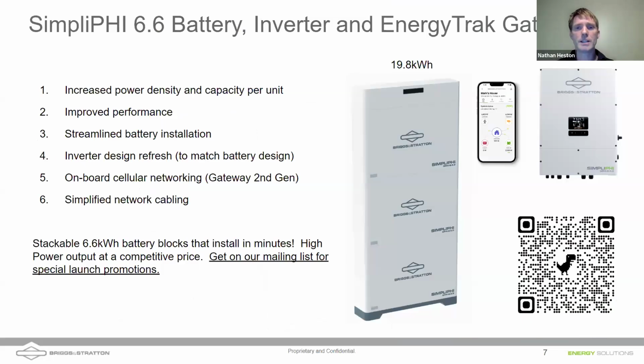So if you're interested in this new battery, it's coming in at a much lower price point for us per kilowatt hour, so there's going to be a lot of savings there. It's also a smaller footprint. I got to interact with this battery this past week. It's about 30 inches wide and about 5 feet tall, and a 20 kilowatt hour stack, like you're seeing there on the screen. And this is going to offer us a greater spectrum of battery offerings for both the Sol-Ark as well as our own inverter.